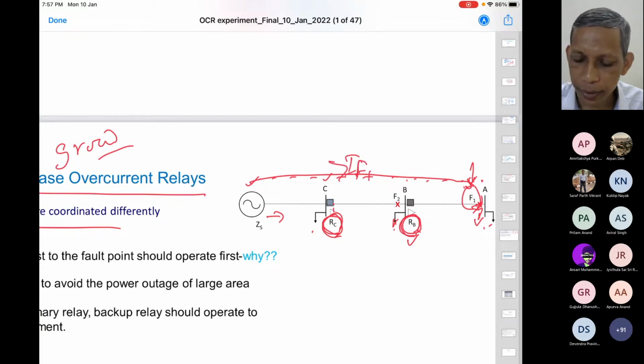Now what will happen? The question is, if they see the same current, who should trip? It may confuse. Who should trip? We say that RB should trip, because if RC trips, this load will not get the supply. But if RB trips, this load will get supply. So from a selectivity perspective, we prefer that RB should operate at that time. Otherwise, unnecessarily some of the loads will be out of operation.